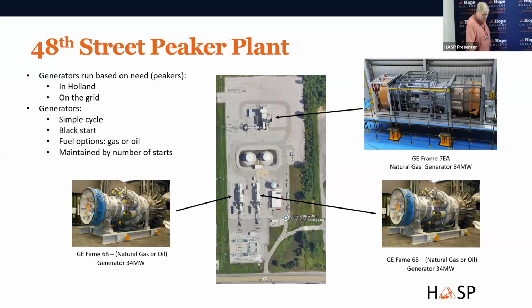They have a feature called black start in the utility business. What happens if the whole network collapses, if something happens and we have to cut ourselves off from the grid? What do you do when there's no electricity? In order to start all this stuff, you need electricity to get it running. So black start capability - the two 34 megawatt generators can start on fuel oil and have enough batteries and other systems so we can start them with no outside energy. The world is dark and we're going to start them up. That's what black start is all about.